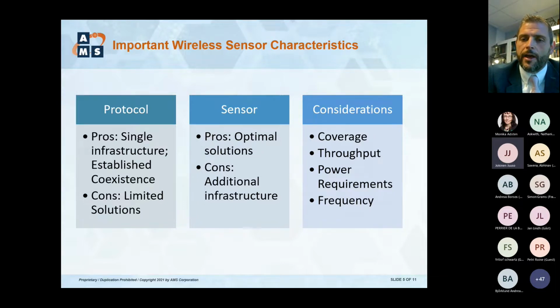And so just some of the other considerations are what type of coverage do you expect to have? Again, if you're only looking to deploy these for certain pumps and motors, well, you only have to have coverage at those locations. So you may only have to have coverage for, say, a wireless HART network over a third of your plant, because that's where you have the pumps and motors that need wireless HART data to be able to get back to your backbone from. Whereas when you deploy Wi-Fi, if that's going to be for your mobile coverage, voice over IP for operators and plant personnel with phones, it's going to have to be pretty much 100% coverage.